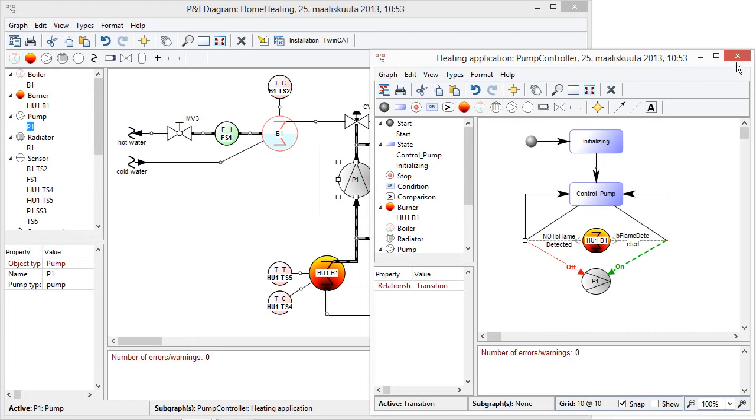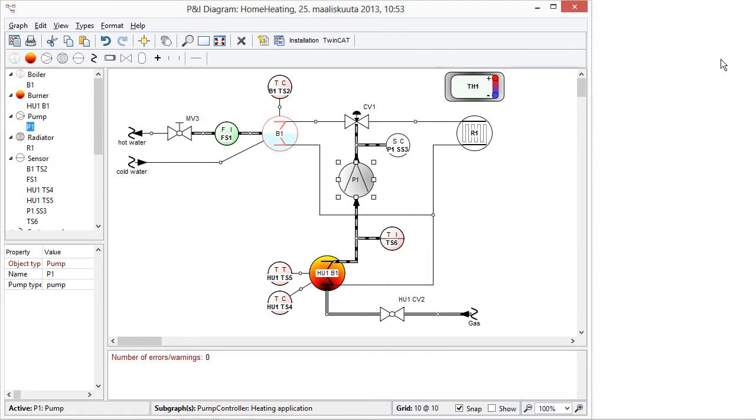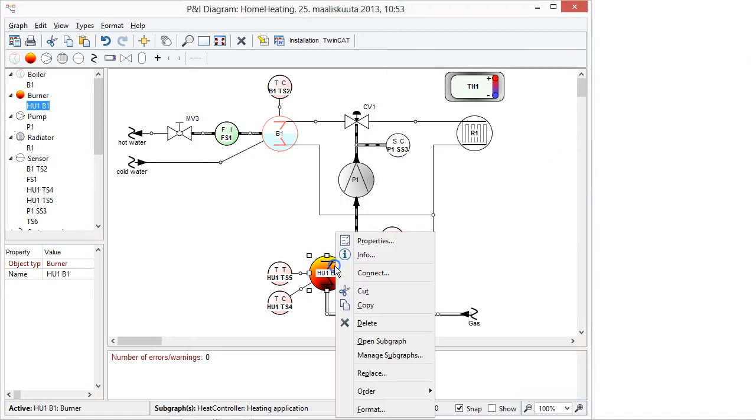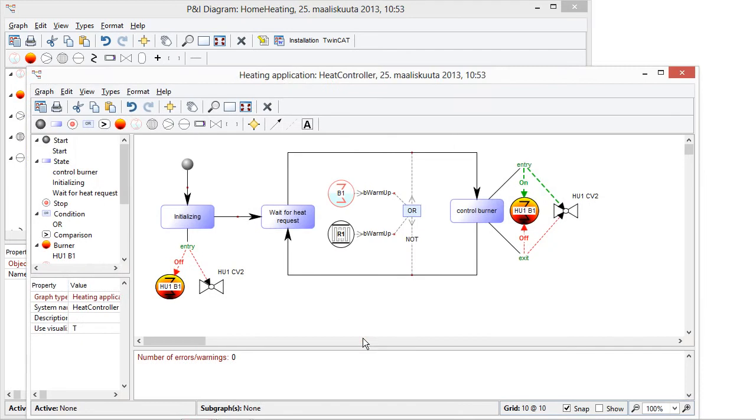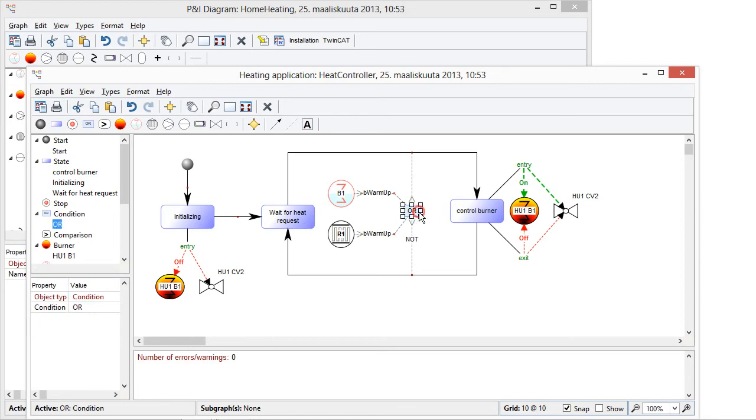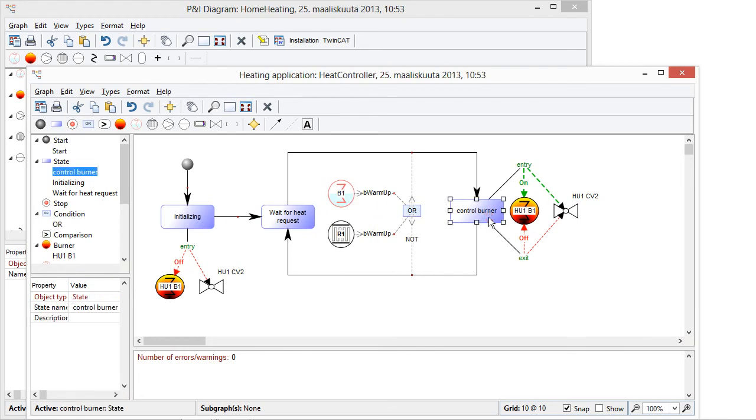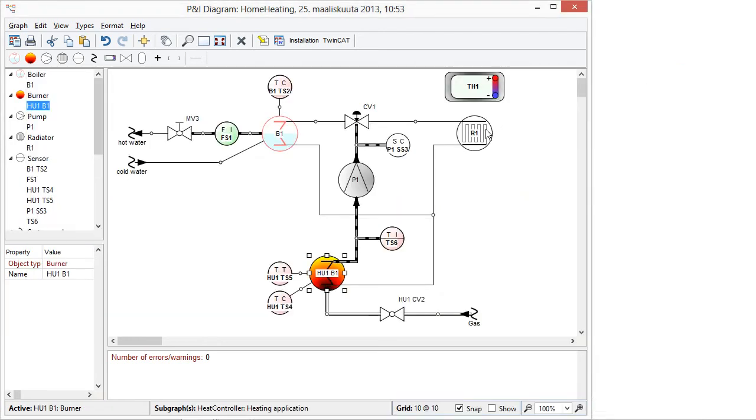In a similar manner there are also other kind of models for describing for example the burner state machine which is more complex. Like how the valves are open and off. And also conditions to combine that if boiler requires to be warmed up or radiator air one requires to be warmed up. Then we call to control burner state. And if there is the negation that not either of them is needed then we call to wait for request.